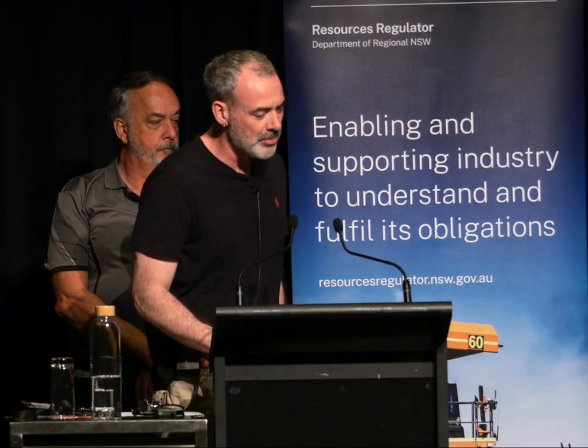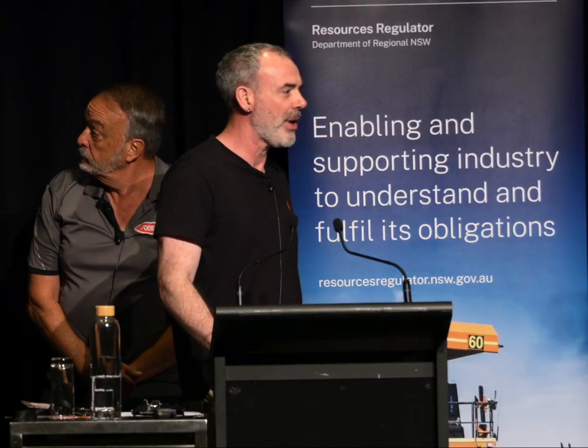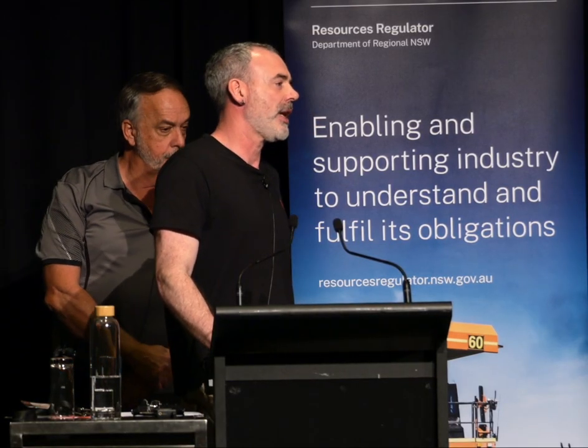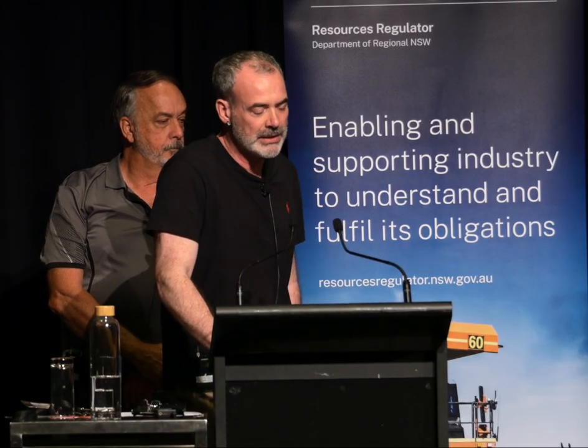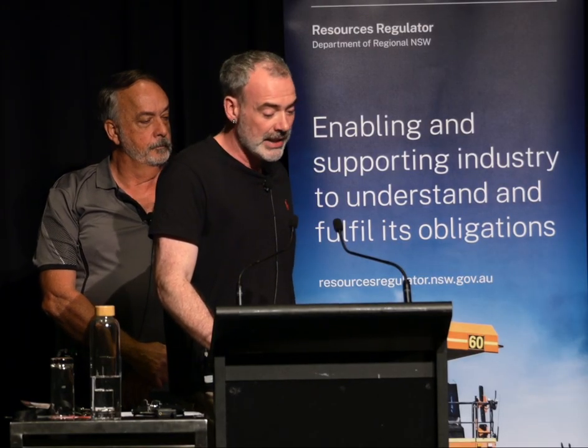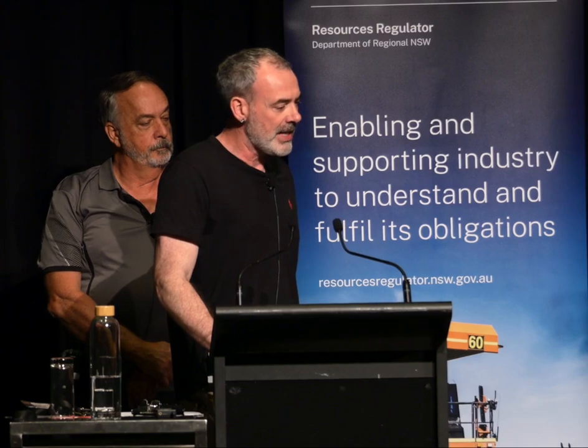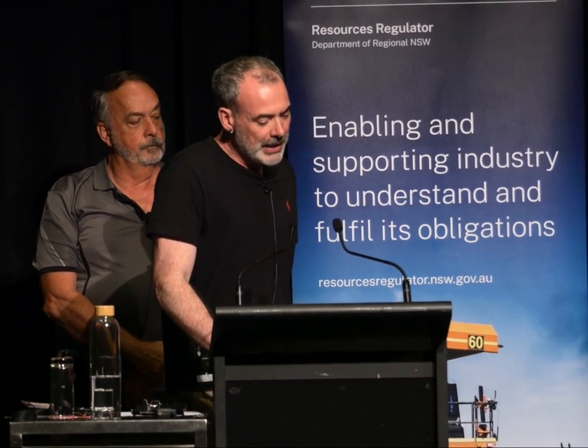Okay. So transformers are critical assets in a power network. A failure of a power transformer can cause a cascading failure. It could cause the lights to go out on a mine site. It could cause a fire, a fatality. So to facilitate a reliable performance, transformers require good insulation systems, which consist of solid insulation or paper, cellulose, and also mainly insulating fluid, alternatives being dry-type transformers.